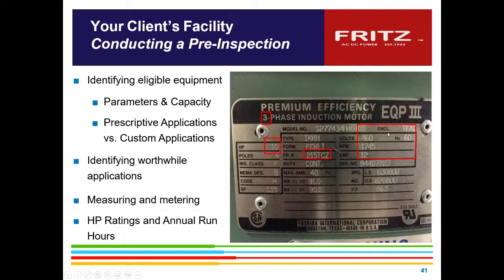So this happened to be an enclosure with a totally enclosed, air over motor. It gives us the frame size. We can look at the horsepower, the RPM and rating. And if we also have an idea of what it's operating, we can tell you what part of your power is running on what part of your facility. So it's not just, okay, I'm going to save a big chunk of money. It's only if you have it applied to the proper applications properly.